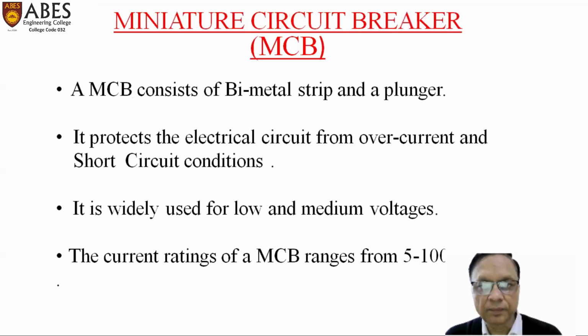Basically, our MCB works on two principles. One is overcurrent and the other is the short circuit condition. Overcurrent is a time prolonged fault. For example, let me take a 10 ampere MCB. The MCB is rated at 10 amperes. Now, if a current of 12 amperes flows instantly, at once, the breaker will not trip. Instead, if that 12 amperes is prolonged, if it is passing through the breaker for a very long period of time, then the breaker will act, or you can say it will trip.